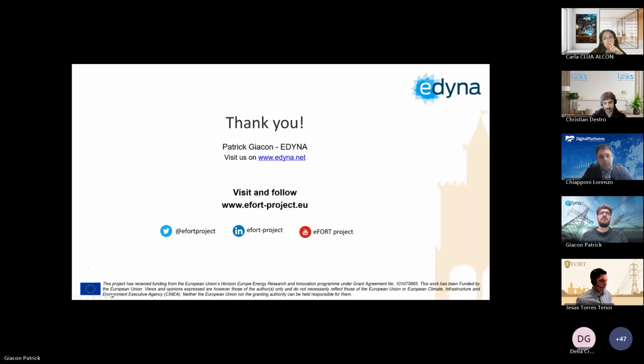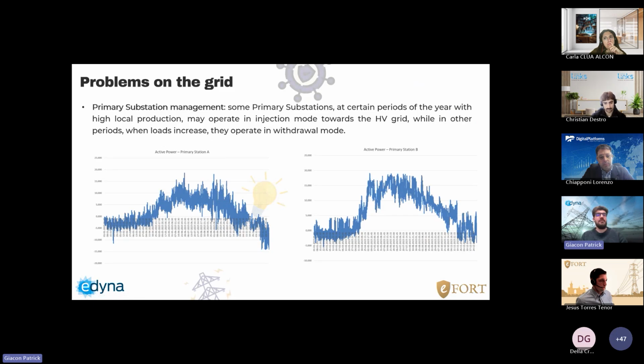Finally, the management of primary substations is becoming complex in some areas, because at certain periods of the year, when local production is very high, some primary substations may operate in injection mode towards the high voltage grid. At other times of the year, when loads increase, they switch to withdrawal mode. Here you can see two examples of primary substations of Edyna. As shown in the graph, positive values correspond to injection mode into the high voltage grid, while negative values correspond to absorption.